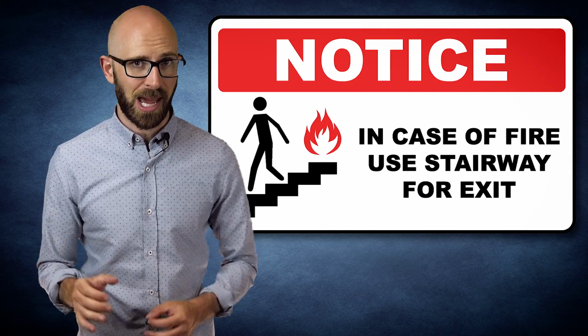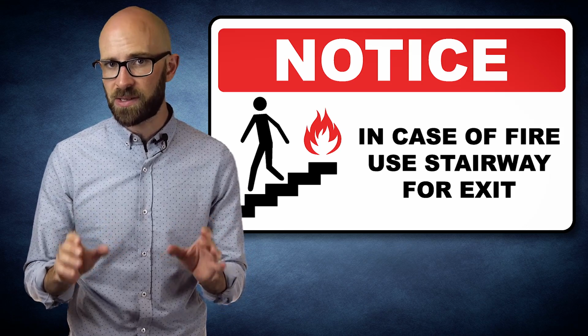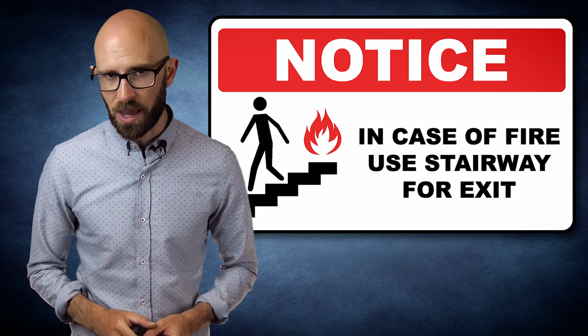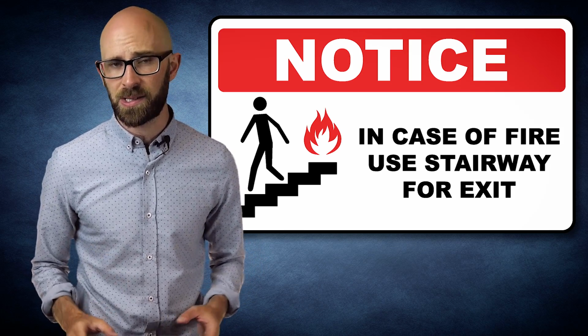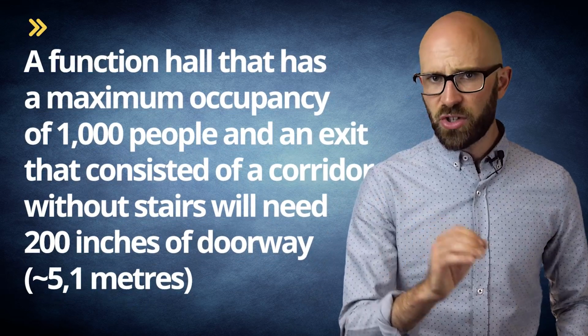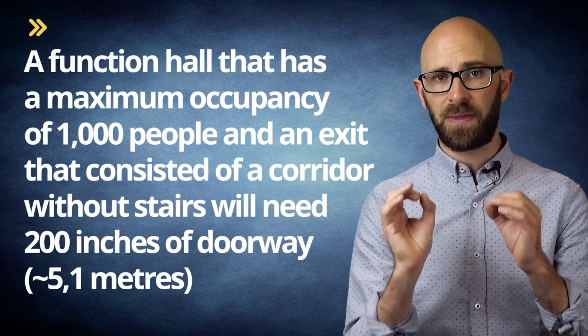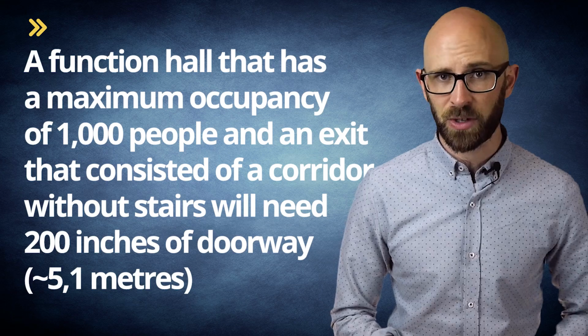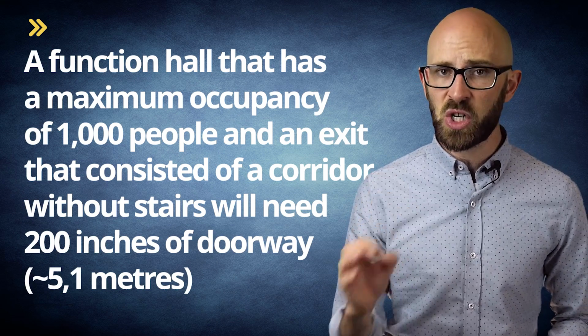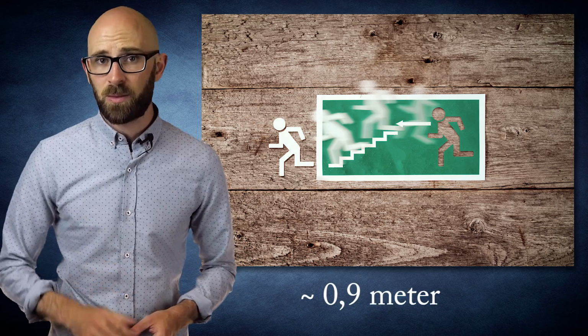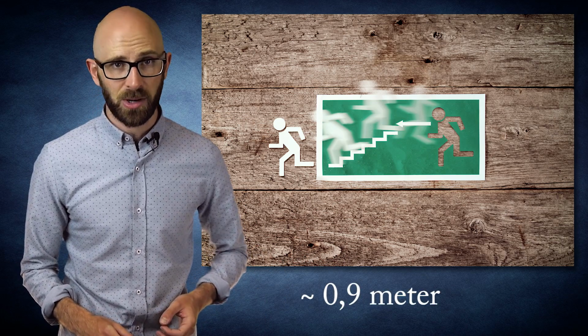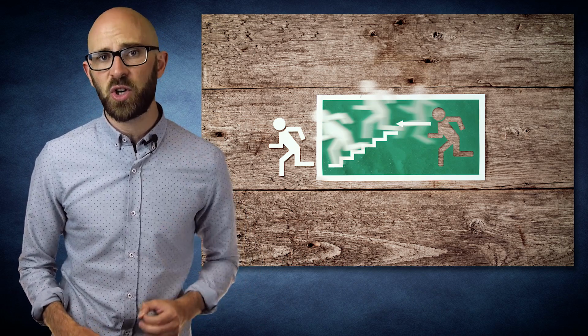Exits that consist of a stairway need to have 0.3 inches of doorway per person, and all other exits need 0.2 inches of doorway per person. So a function hall that has a maximum occupancy of 1,000 people and an exit that consisted of a corridor without stairs will need 200 inches of doorway. With doorways at about 36 inches in width, wider than the Americans with Disabilities Act requires in the United States, that function hall would need approximately 6 such doors.